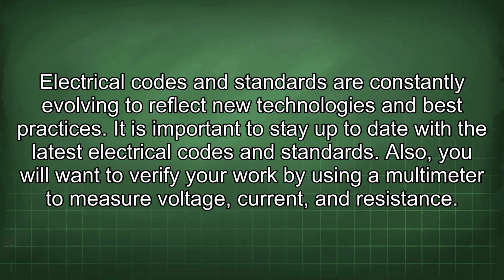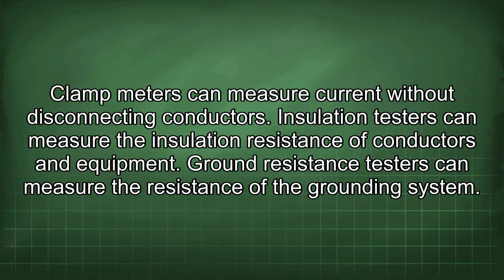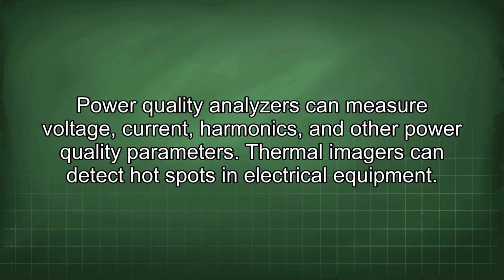Also, you will want to verify your work by using a multimeter to measure voltage, current, and resistance. Clamp meters can measure current without disconnecting conductors. Insulation testers can measure the insulation resistance of conductors and equipment. Ground resistance testers can measure the resistance of the grounding system. Power quality analyzers can measure voltage, current, harmonics, and other power quality parameters. Thermal imagers can detect hot spots in electrical equipment.